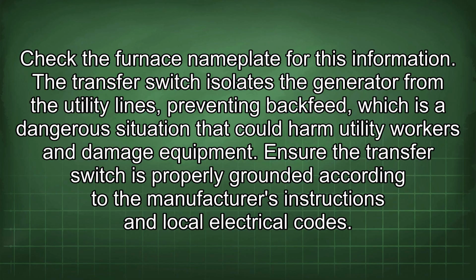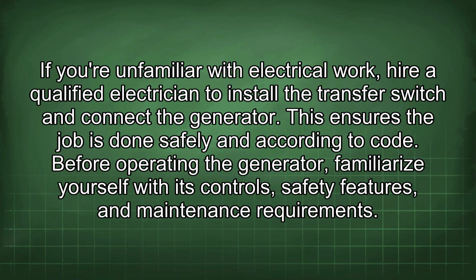The transfer switch isolates the generator from the utility lines, preventing backfeed, which is a dangerous situation that could harm utility workers and damage equipment. Ensure the transfer switch is properly grounded according to the manufacturer's instructions and local electrical codes. If you're unfamiliar with electrical work, hire a qualified electrician to install the transfer switch and connect the generator. This ensures the job is done safely and according to code.